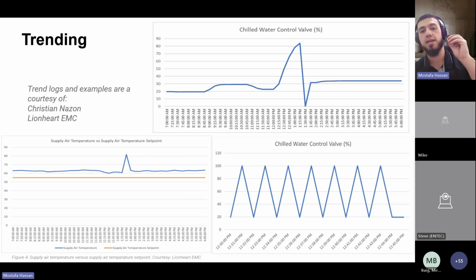The economizer damper is dedicated to maintaining the supply air temperature. We're going to show that soon. A set point of 60 degrees Fahrenheit. Because this is an integrated economizer, there are periods of time in which it works in tandem with the chilled water control valve to support the supply air temperature control towards set point. There is your supply air temperature trend log, right? And all these are trended over 15-minute intervals, right?